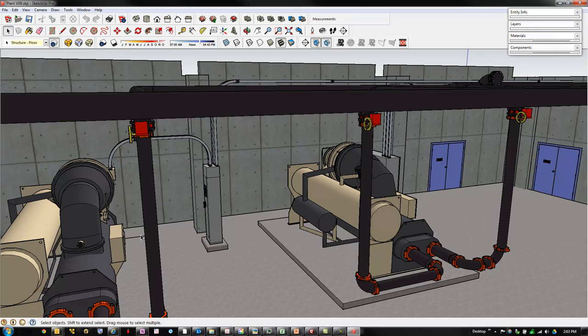So you don't know this for sure, but if you were walking around looking at this plant and saw these things, you would conclude, oh, I bet the designer intended for this machine to carry the load under low load conditions. Again, just say it was a 600 ton machine. Well, the idea probably was below 600 tons, this machine runs. And as it unloads, eventually it starts using hot gas bypass, slowing down with a variable speed drive, but it can follow the load right down to minimum.